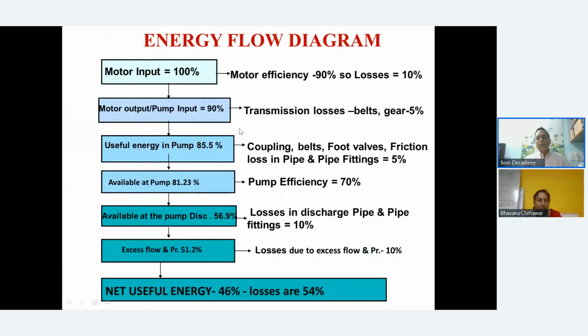Now, typically, what is the energy that you input to the pump? If you input 100 units of energy to the motor, and we consider motor efficiency as 90%, what is the motor output? You're getting only 90% of the 100 units. Then there are transmission losses, belt, gears, etc. You get about 5% loss, so with a further 5% reduction, the useful energy to the pump is only about 85.5%. Again, there are coupling losses, the foot valve losses, friction losses, etc.